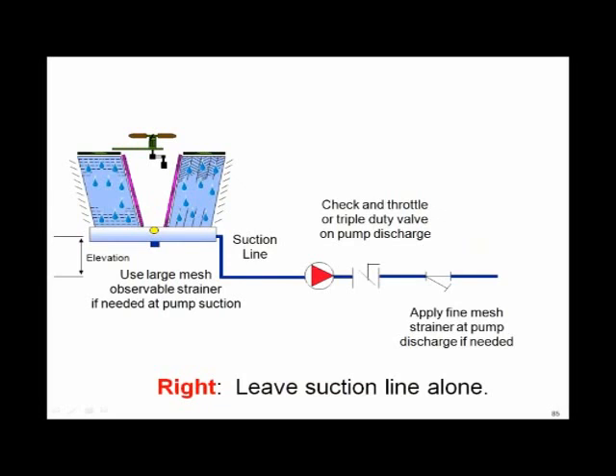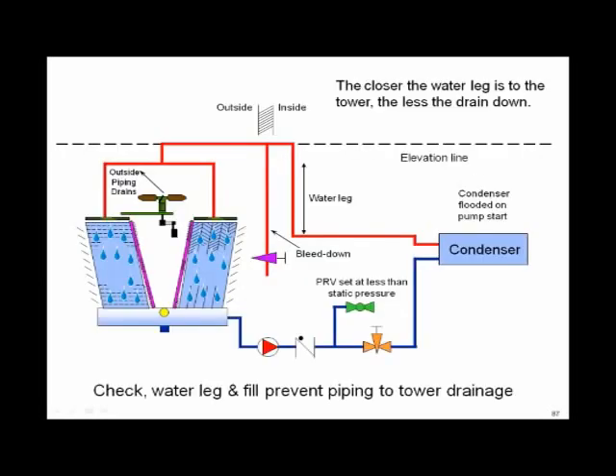If you want the rules of thumb again, leave the suction lines alone, please. Keep the pressure drop between the suction of the pump and the tower at or under 5 feet. Please keep it clean. If you got any valving, put it on the discharge side of the pump. A little bit on the discharge pipe. And this is another little pet peeve of mine, called a water leg. And we got a triple duty valve on the pump here. And I turn that pump off. Where's the water going to go?